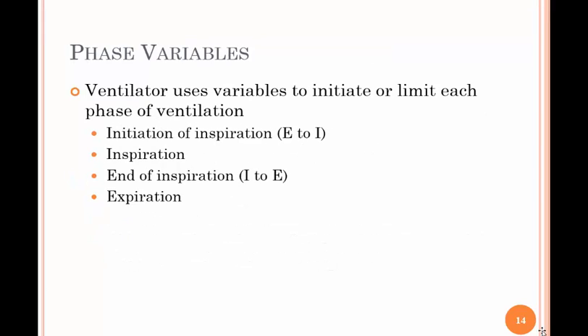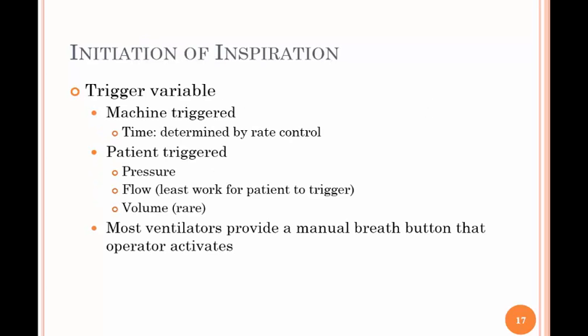Phase variables are used to initiate or limit each phase of ventilation: the initiation of inspiration, the inspiration itself, and the end of inspiration. The trigger variable initiates the breath — it can be machine or patient triggered. In the machine trigger, the variable is time, determined by the rate control. If the rate is set at 10 breaths per minute, the machine will deliver an inspiration every six seconds. If it's patient triggered, it can be pressure or flow.